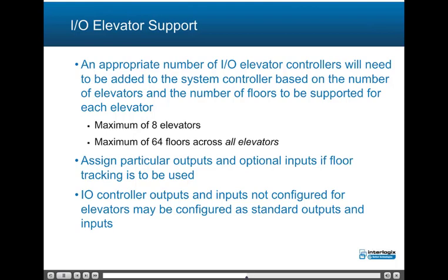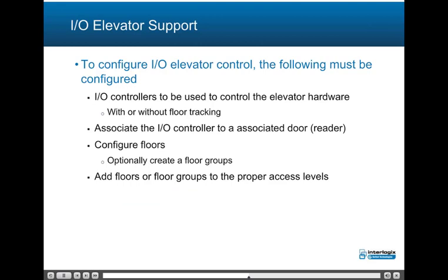For relay input-based IO elevator support, an appropriate number of IO elevator controllers will need to be added to the system controller based on the number of elevators and floors to be supported. The system supports a maximum of 8 elevators and a maximum of 64 floors across all elevators. Next, assign particular outputs and optionally inputs if floor tracking is to be used — floor tracking will report as part of the event what floor was accessed by a particular credential. IO controller outputs and inputs not configured for elevators may be configured as standard outputs and inputs. To configure IO elevator control, configure IO controllers to be used to control the elevator hardware with or without floor tracking, then associate the IO controller to the associated door and reader, configure floors, optionally create floor groups, and then add floors or floor groups to the proper access levels.